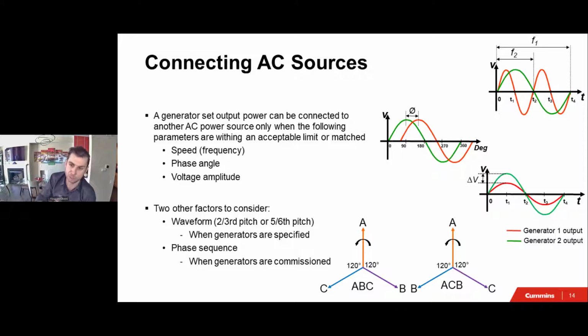Obviously, the manufacturer will make sure that it's a 2/3 pitch, and most generators out there are 2/3 pitch, but some are not. The issue comes in if you already have a genset in the field and you're doing an expansion. So maybe you have an application with the first two gensets you installed, those two were installed in the 1950s, and then two more were added in the 1970s, and now you're going to buy two more generators today.